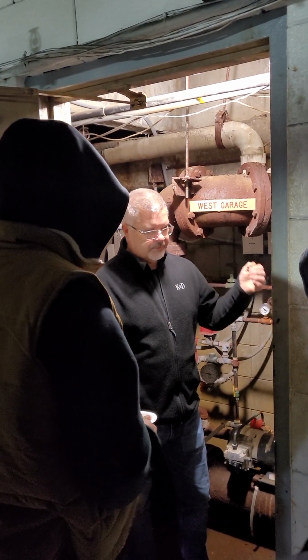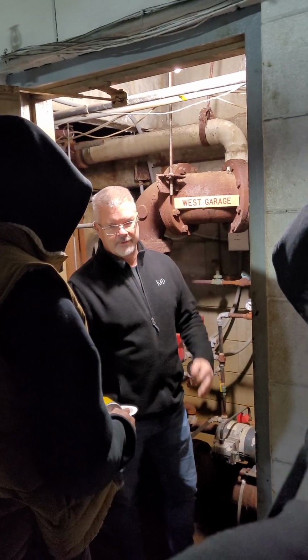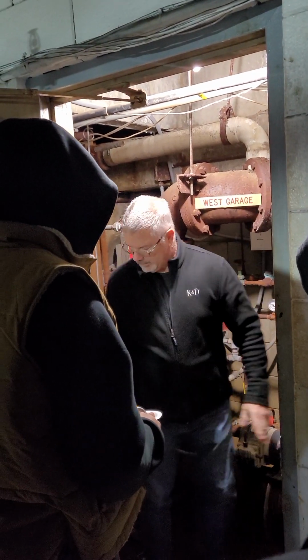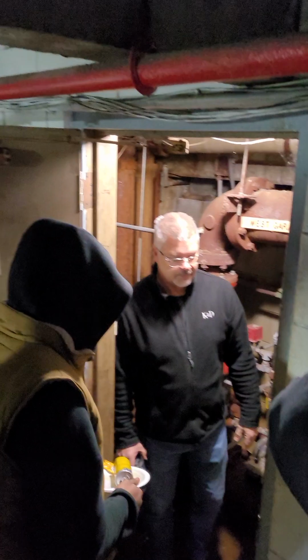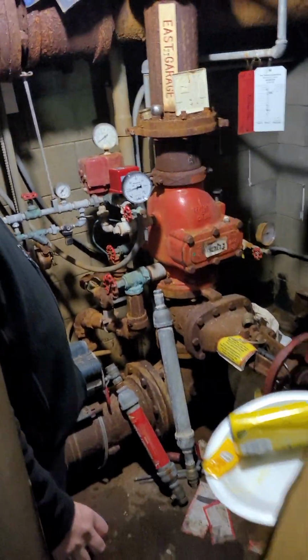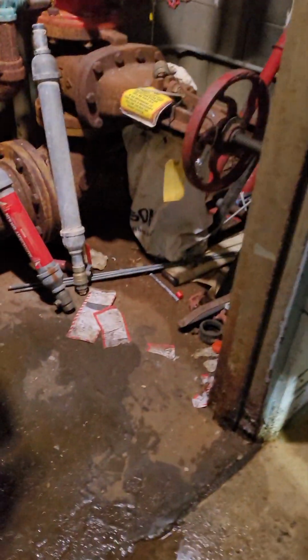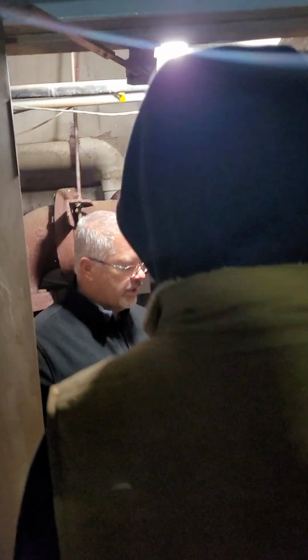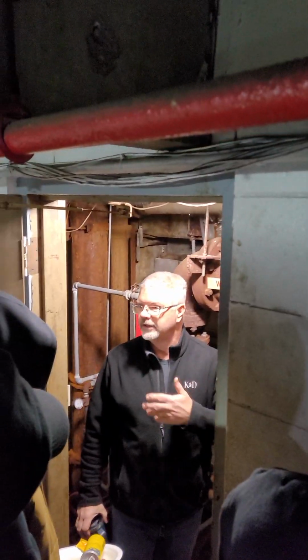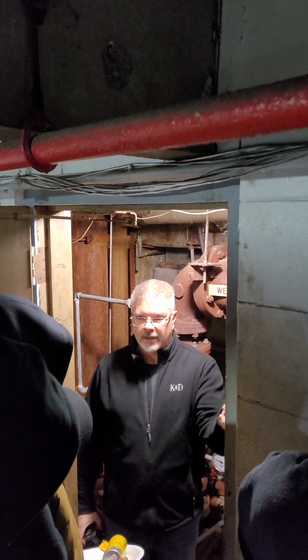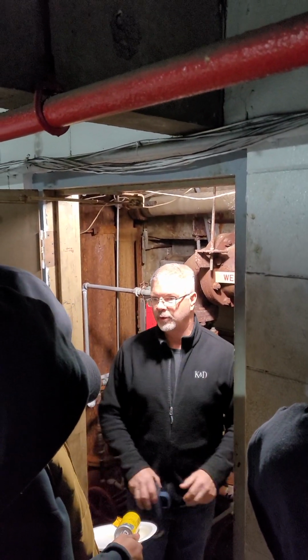The biggest thing is if you get a call for the parking garage and water coming out of the pipes, it's these 2 valves here. That's the 2 valves, the switch for the compressor, that is the only way you're gonna stop water from coming to this level. Every level of this garage has 2 of these, so it's not very hard to find. If you've got water coming on this level, these 2 will stop it.